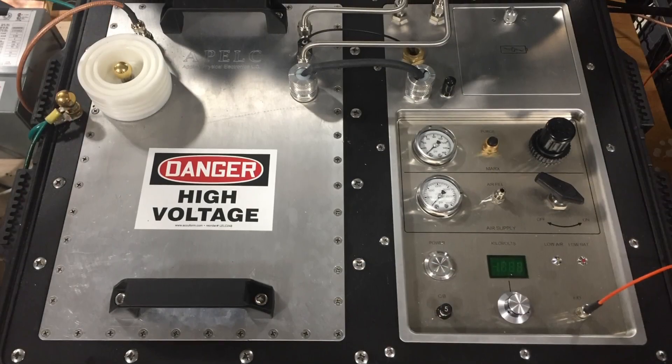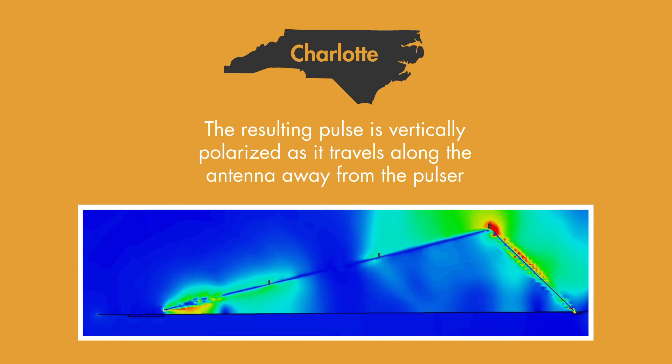Devices under test are powered up, then subjected to an EMP wave or surge. The Charlotte facility can produce a 50 kilovolts per meter pulse generated by a 13-stage Marx generator, which is then injected into a large antenna structure.